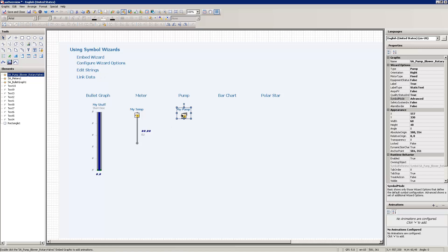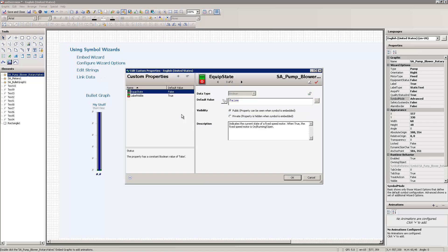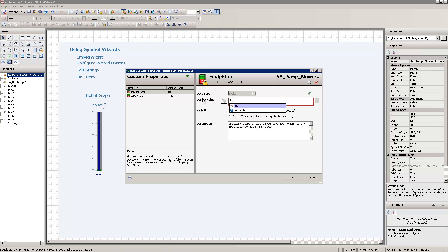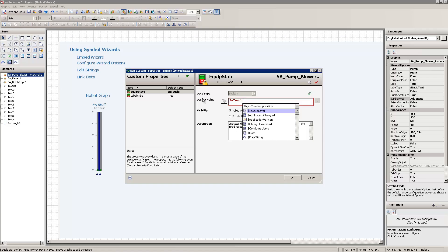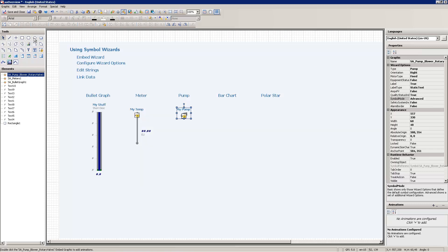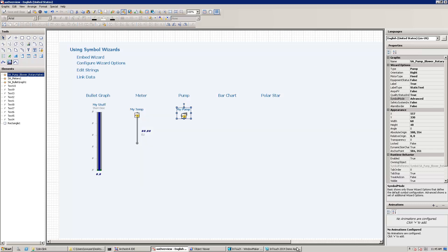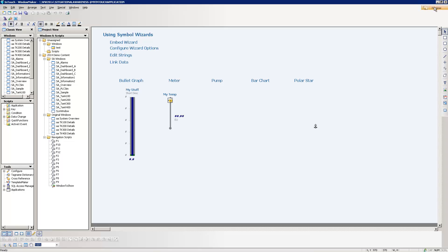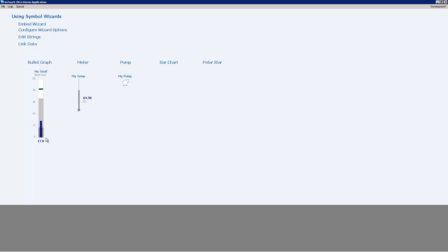I am going to link the data. Again, I'm going to go to the custom properties on this one, which is Ctrl M. In this particular case, the equipment state here, which is defaulting, is false. I'm going to change that, and what I'll do is I'll use that InTouch tag again, the InTouch colon dollar second, and I'll say only when you're greater than 30, just to give me a Boolean result. So now I should go ahead and save that, make sure that that's working. And you can see that my pump here, you can see it just changed because it's swapped over. So it's going to show white, which is the passive state when it's less than 30, and it'll show gray, which is the active state when it's greater than 30. I'll come back a little bit later, and we'll see that that changes there rather than making you watch it 20 seconds.